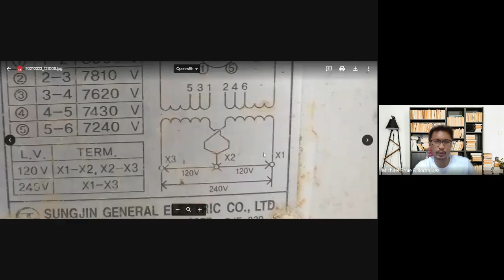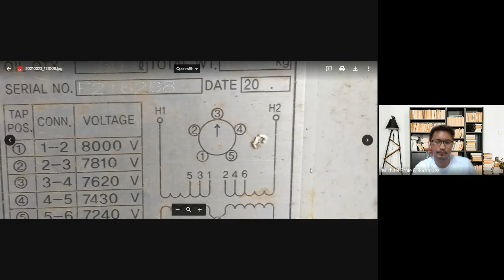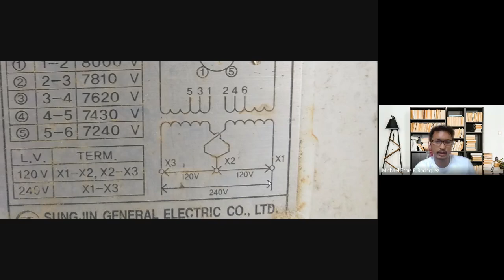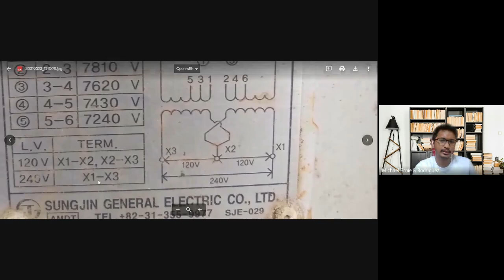So when connecting a single phase transformer, on the primary side you take H1, H2 is grounded, and then you connect H1 to X1. And X3 is also grounded. So to get 240 volts, I mean 240 volts as your voltage, you use the terminals X1 and X3 -- because if you use X1, X2, that's only 120 volts.